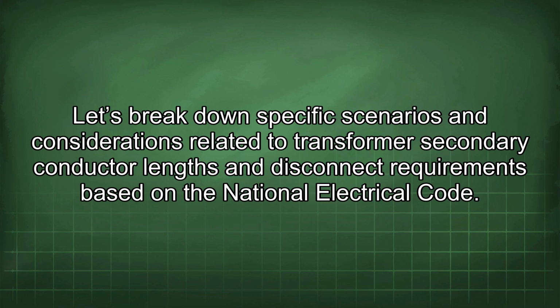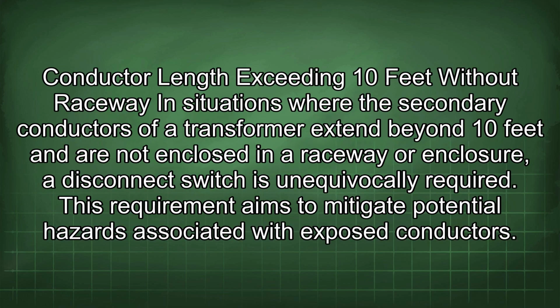Let's break down specific scenarios and considerations related to transformer secondary conductor lengths and disconnect requirements based on the National Electrical Code. Conductor length exceeding 10 feet without raceway: in situations where the secondary conductors of a transformer extend beyond 10 feet and are not enclosed in a raceway or enclosure, a disconnect switch is unequivocally required. This requirement aims to mitigate potential hazards associated with exposed conductors.